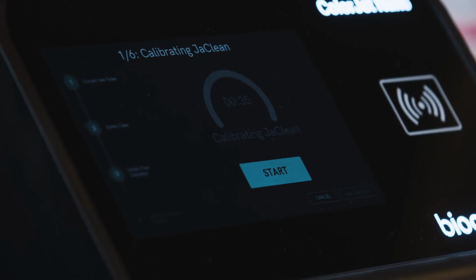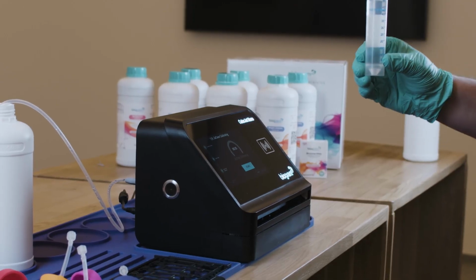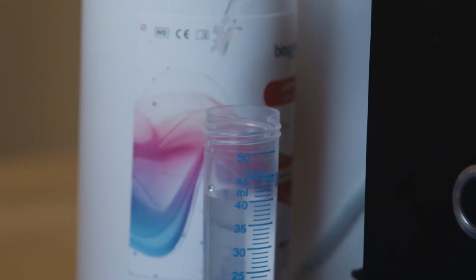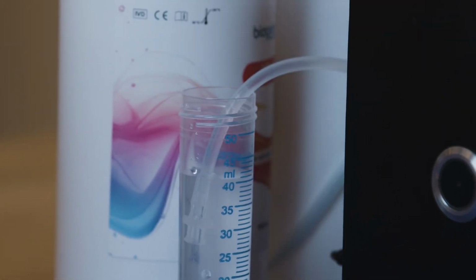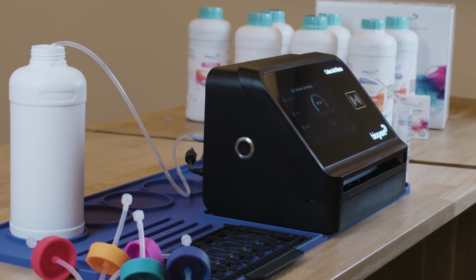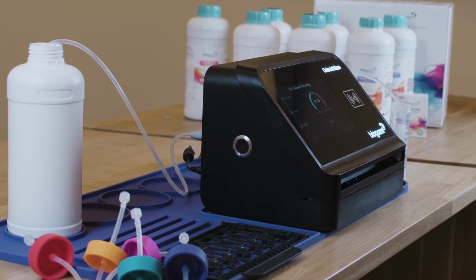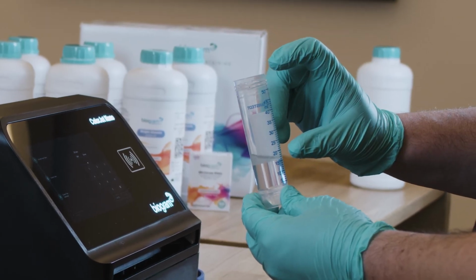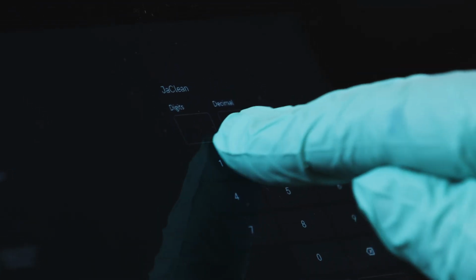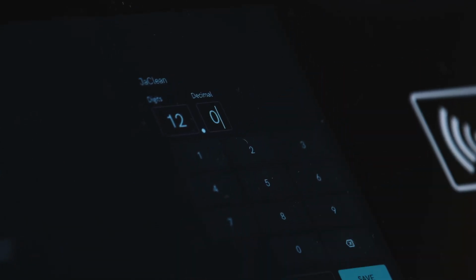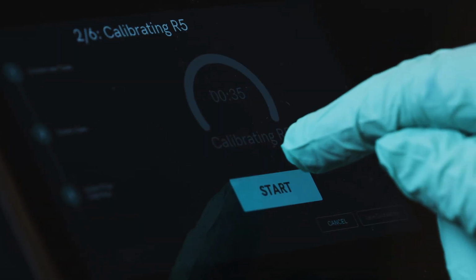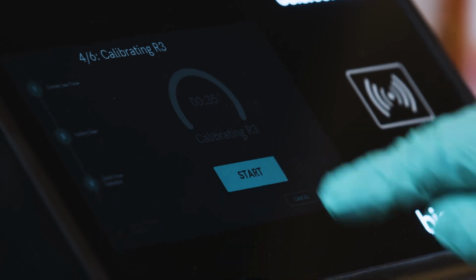Begin the step-by-step valve calibration. Fill a 40 milliliters container or similar with 1 milliliter scale. Start the calibration process. Enter the consumed amount in the interface and record it in the IQ, OQ, PQ document or notebook. Save the calibration and repeat for all remaining valves.